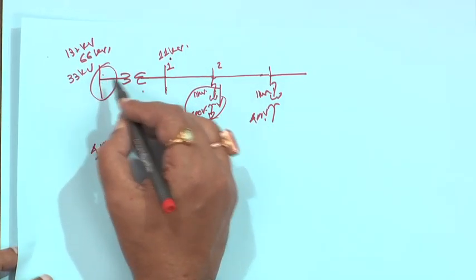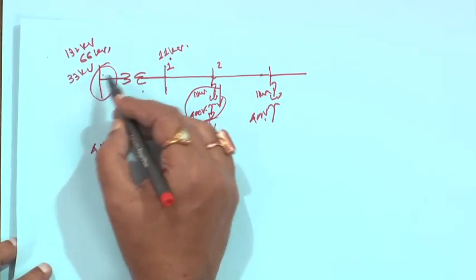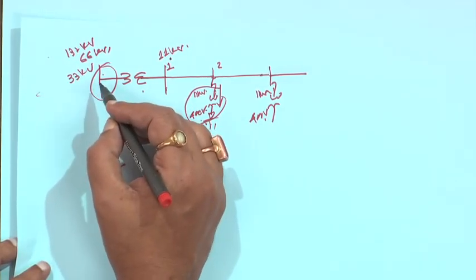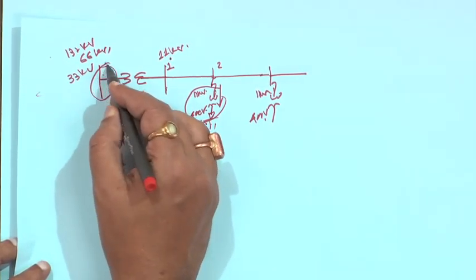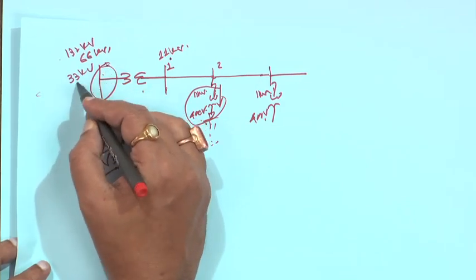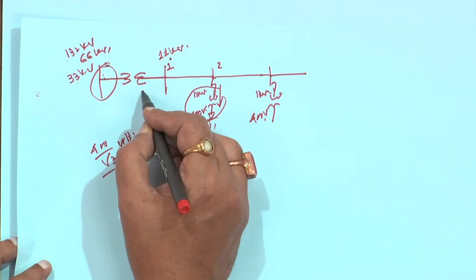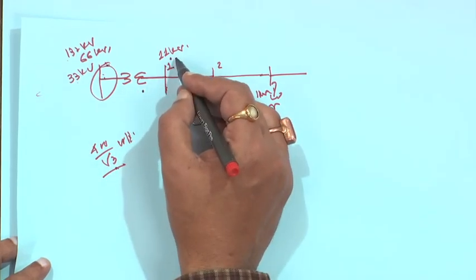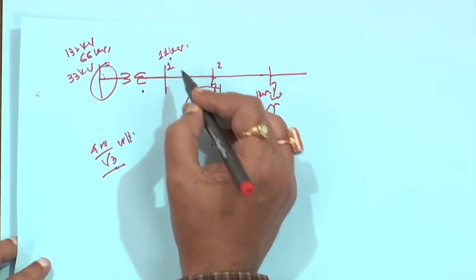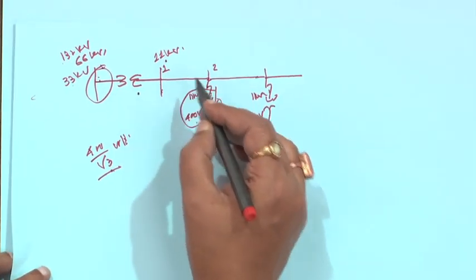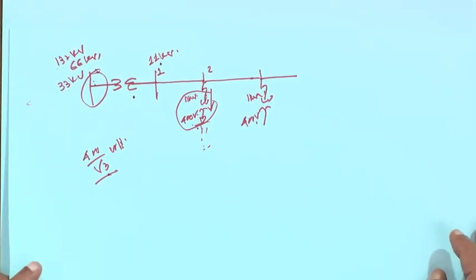And why is it below 11 kV? Because when that power is coming through the transmission line, there must be some voltage drop along the line. So, this side voltage may not be 66 or 33 or 130, it will be less than that. But transformers have the tap changer, you can change the tap and make it approximately 11 kV also, right.